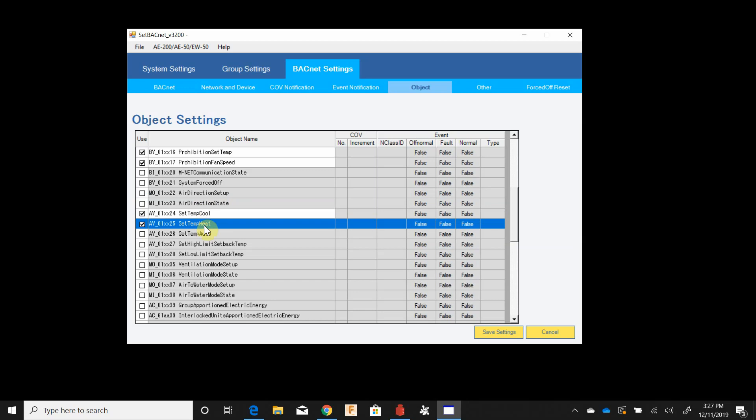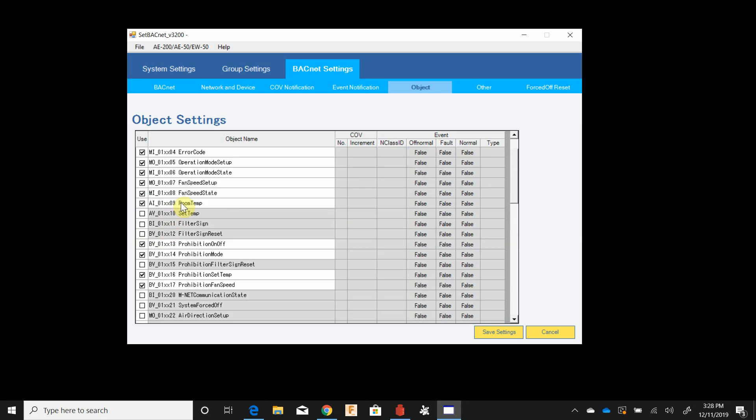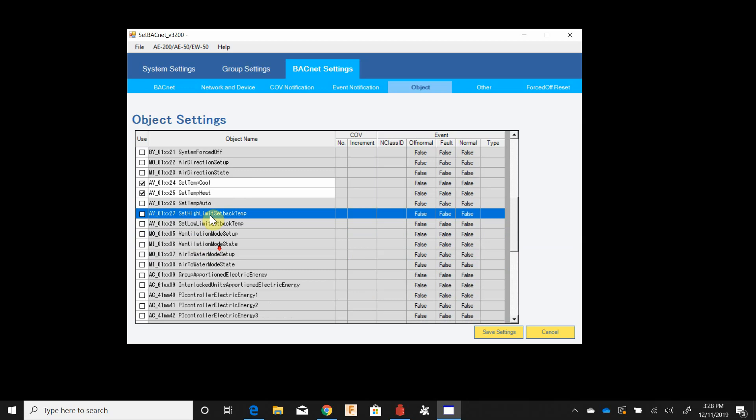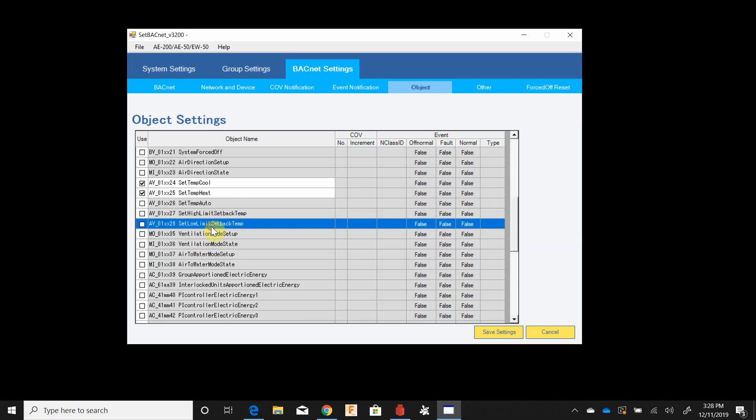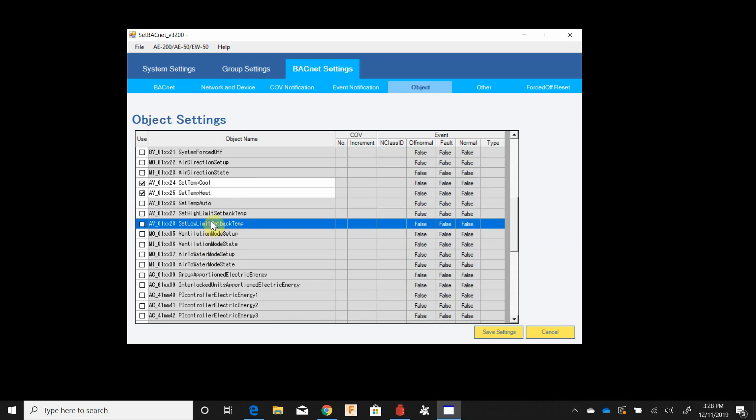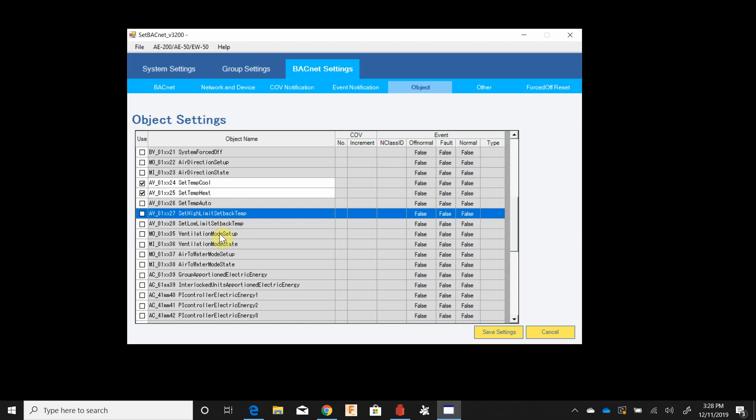Set temp cool and set temp heat are applicable if you're doing dual set point control, which is the default for all thermostats. If you're going to be using that, set temp auto is the one you would use, not this set temp up here, this is only for old model compatibility mode. High limit and low limit setback temps are if you're using the setback function of the AE-200. Generally if the building contractor's integrating this they're not, they're going to write their own setback sequence because they don't want to see that the unit is on during unoccupied hours even though it's in a setback mode.